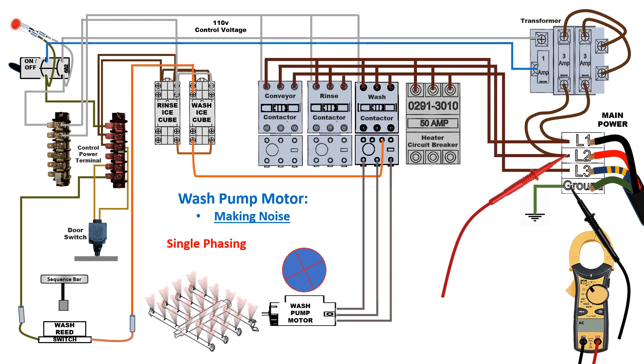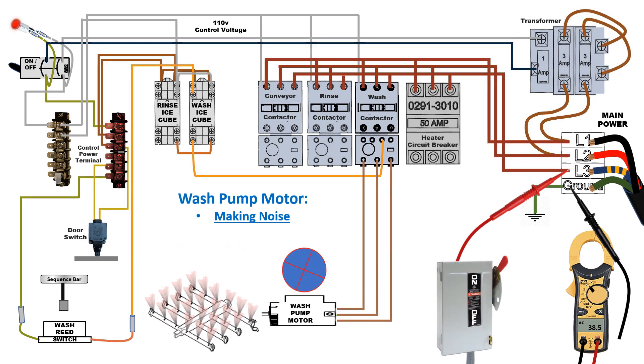We now use our multimeter, again set to ground, and we test L1, L2, L3. We verify if we lost the leg or are we single phasing coming in through main power. And as you can see, we have also lost the leg here.